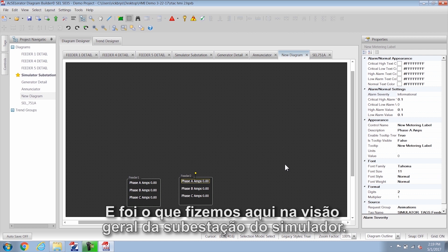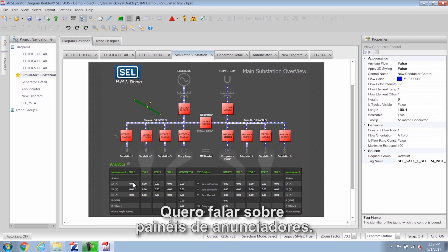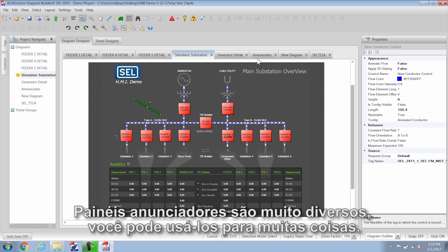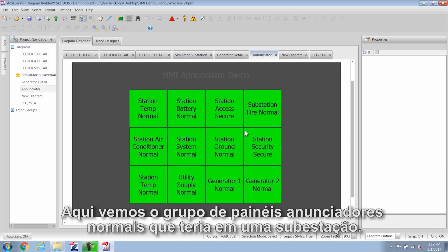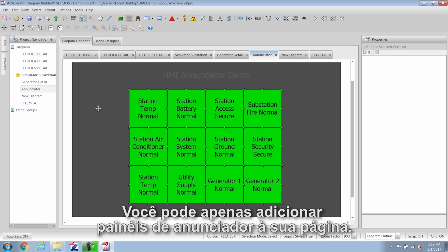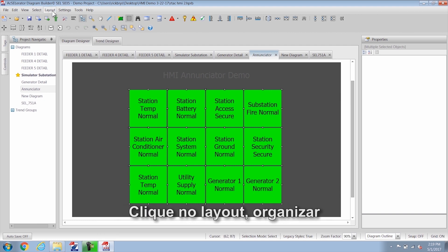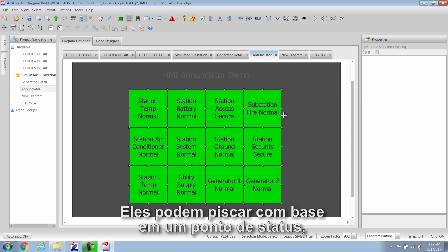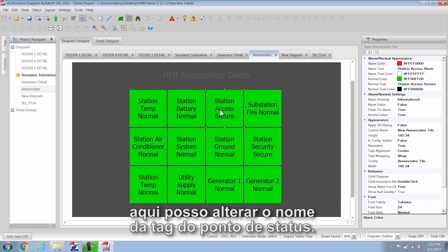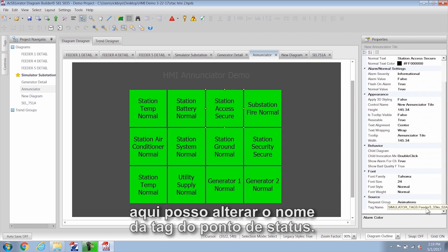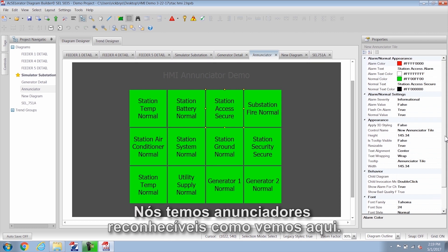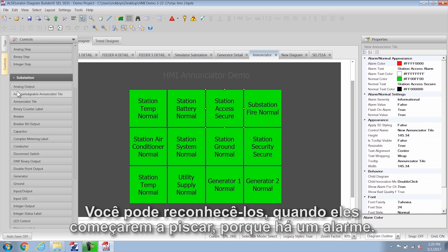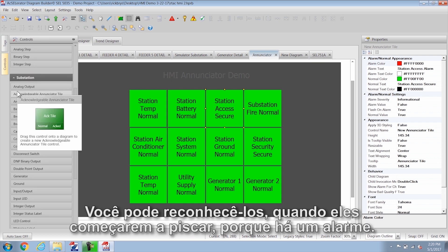That's what we did on the simulator substation overview. Next I want to talk about annunciator panels — they're very diverse and you can use them for a lot of things. Here we see a normal annunciator panel group you'd have in a substation. You can add annunciator panels to your page, click on layout and arrange, and you can arrange by rows or columns so you don't have to drag them into place. They can flash based on a status point, and you can change the tag name of that status point and also change the color. We also have acknowledgeable annunciator tiles that you can acknowledge when they start flashing because they're in alarm.